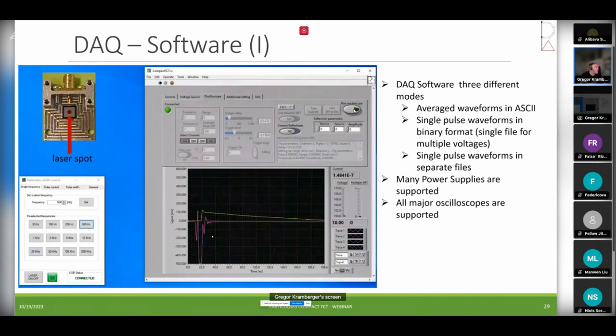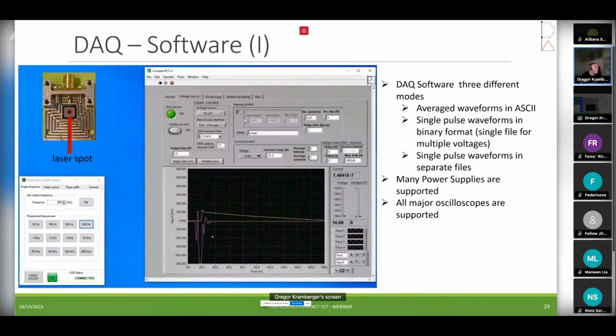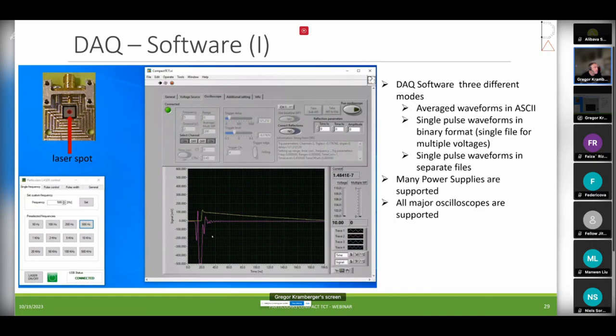And now we'll see, for example in this case, how one of these voltage scans looks like. So you'll see how the pulse actually changes. We go from 0 to 100 volts on this device. Remember, the full depletion is around 18-20 volts. And we go to 200 volts, and you will see how the pulse changes, and what I just explained a short while ago will be shown also on the display.